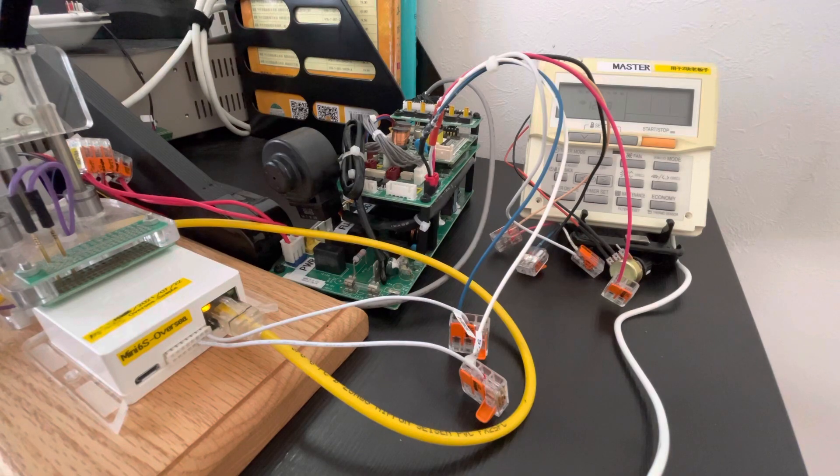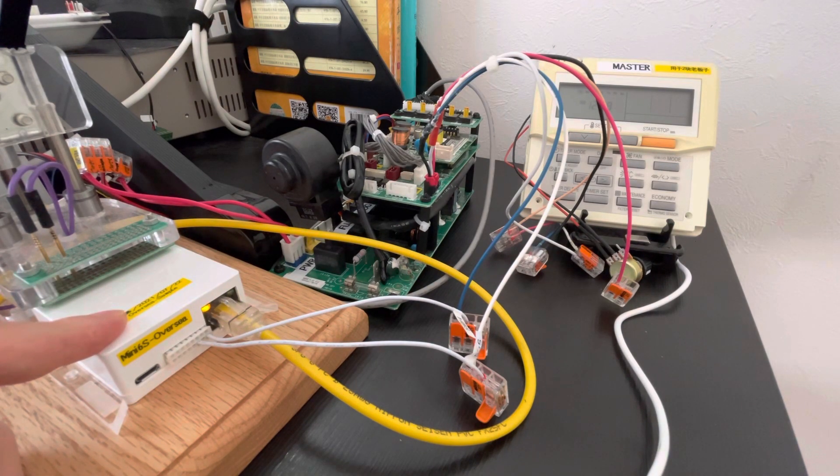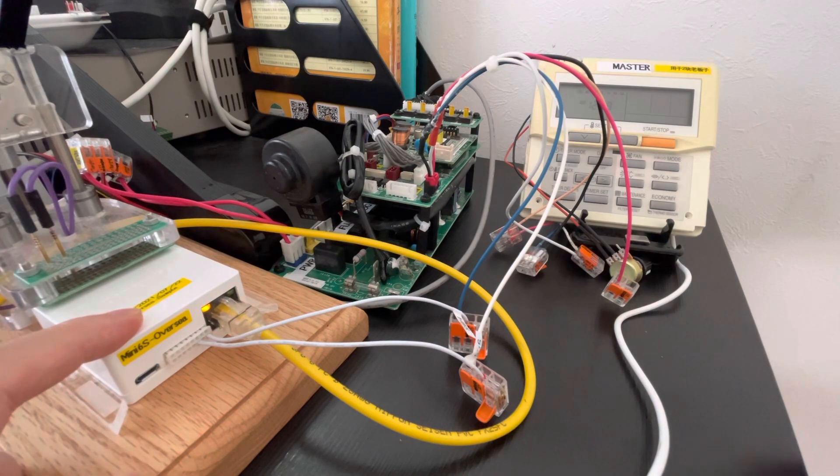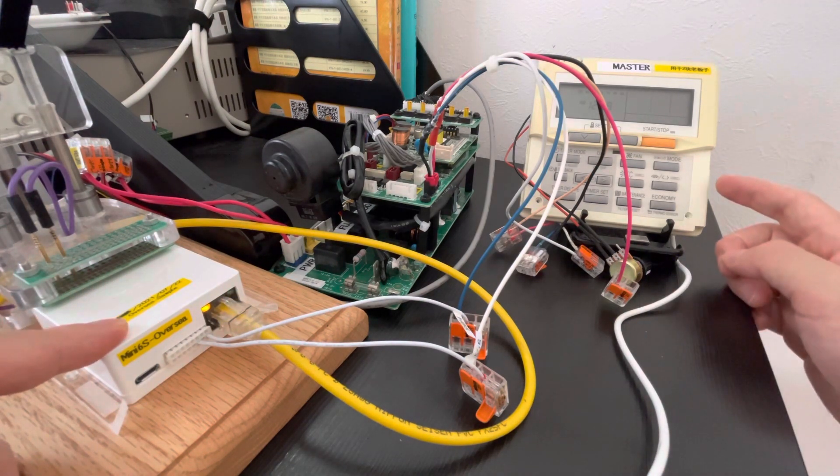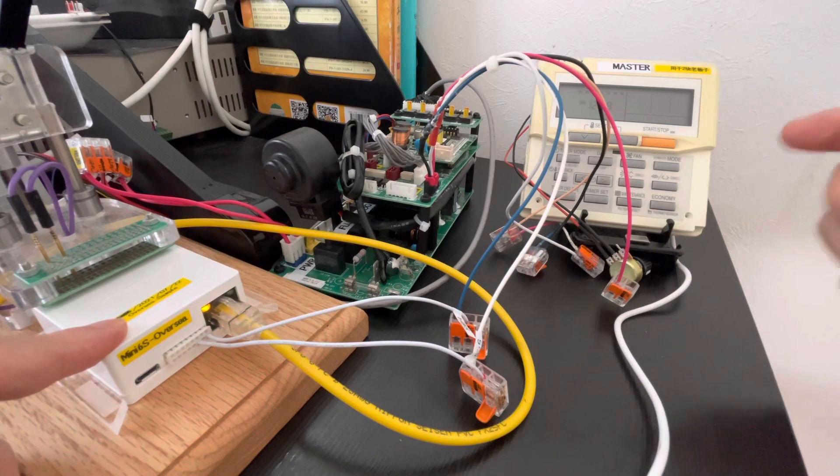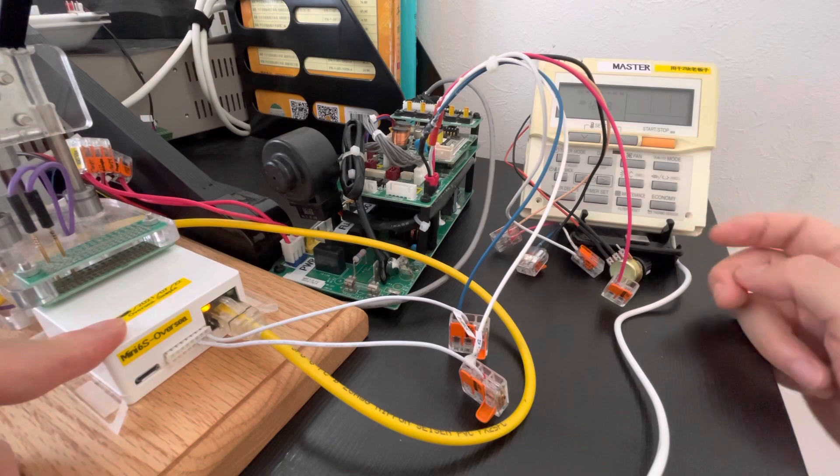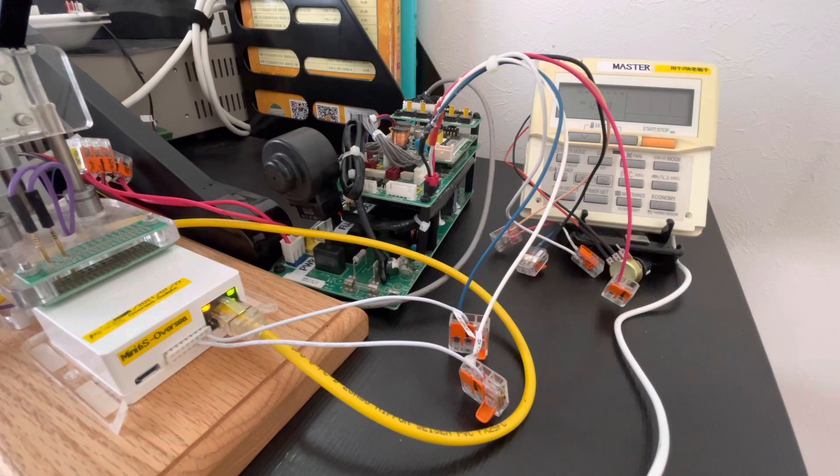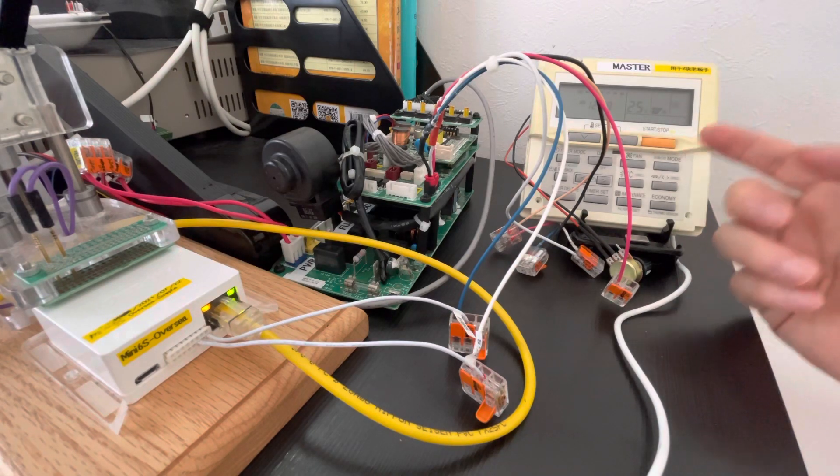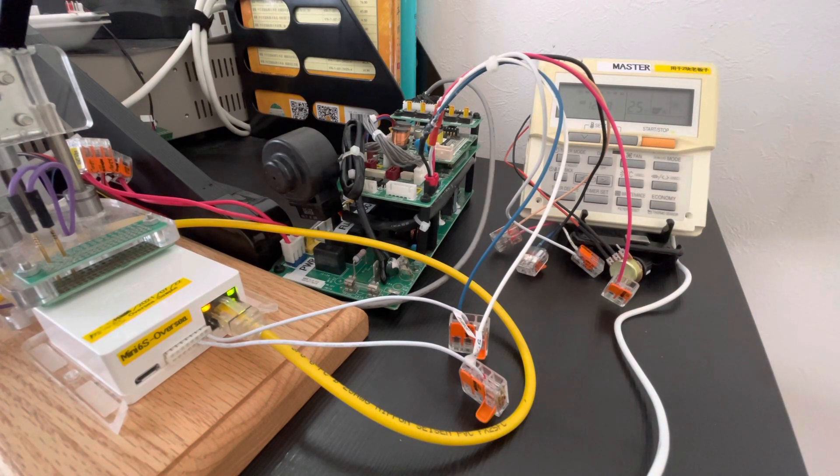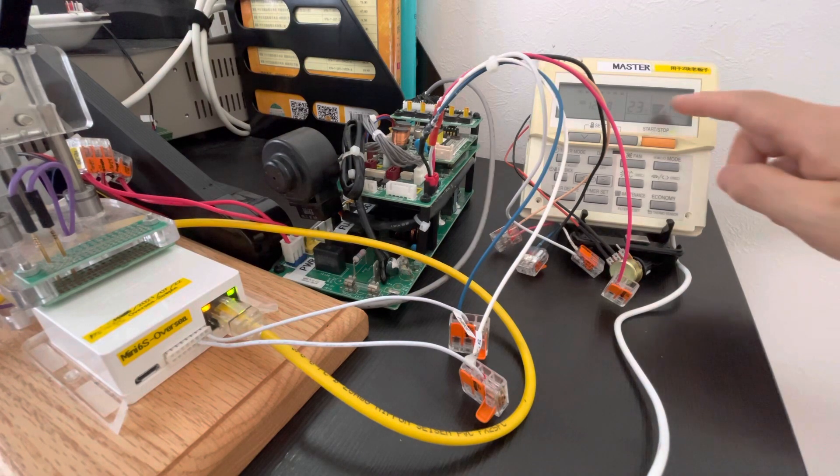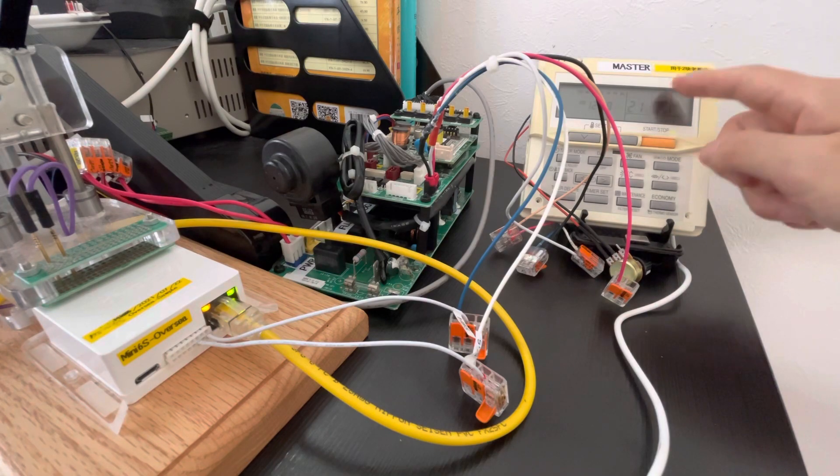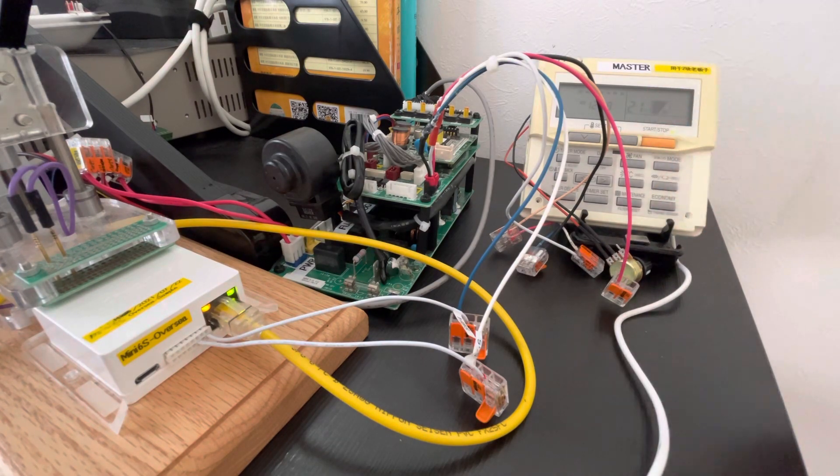For the new solution, our adapter can act as a slave, which is our recommendation. The adapter connects with the original thermostat together, so the original thermostat can act as a monitor. It can show the state of the indoor unit. When the Nest is on, the original thermostat is on, and we can see the fan speed mode. No problem. This is high speed, this is middle speed, high speed, and the setting temperature.